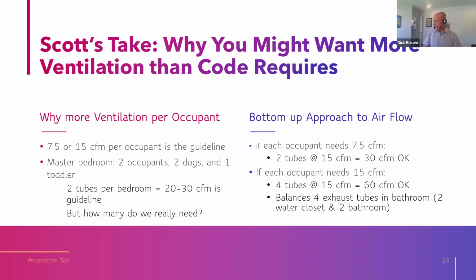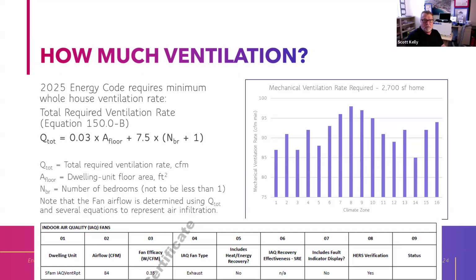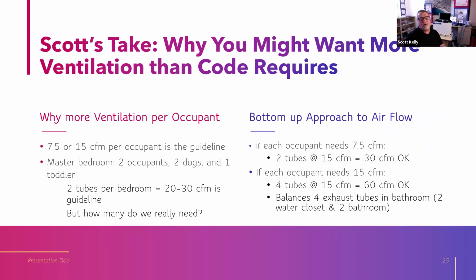Scott, tell us why you think Title 24 maybe doesn't require as much airflow as you think. Okay, go back one slide, please. See in the lower left-hand corner, 02 airflow CFM 84? That's the calculation that's in the plan set, right? Yes. Okay. So let's take that number, and I'm saying that number, I believe, is too low. So let's take this other scenario.